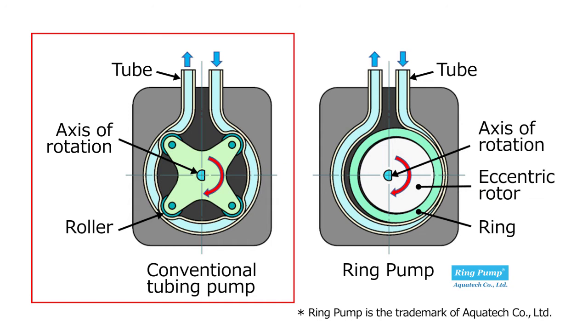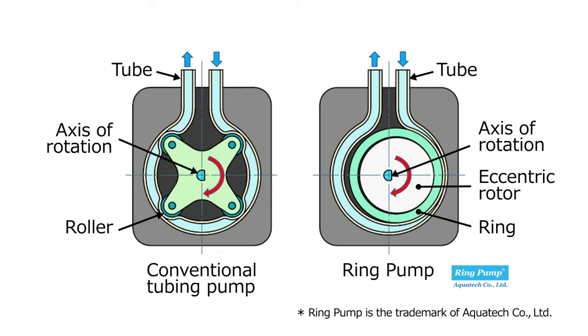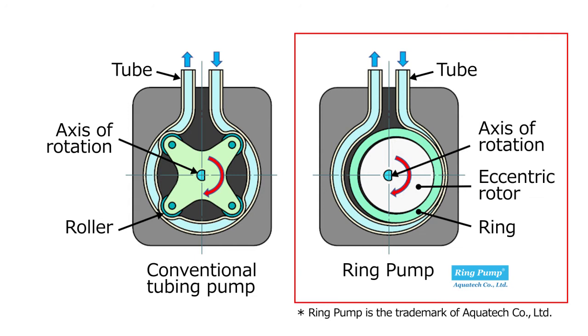Being tightly squeezed by the small rollers, the tube needs to be replaced in a short period of time. However, as the picture shows on the right, the ring pumps that we offer have a big ring, forcing the fluid to move through the tube in a gentle way. Lubricant is added between the ring and the tube to reduce friction. Based on these two improvements, the tube is allowed to be used for a longer time.